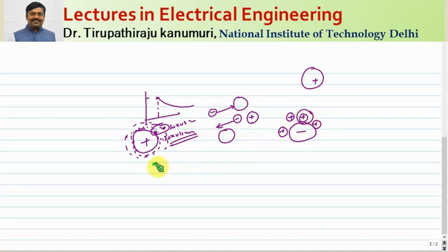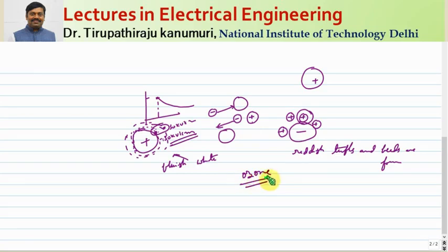So practically, if you are applying DC, a bluish white color will come on the positive conductor, and here the mobility of these carriers is very low. So it will not form a uniform circular ring, it will form tufts. It will be reddish in color, and tufts and beads are formed. Along with that, it also produces some gas. That gas is called ozone gas.